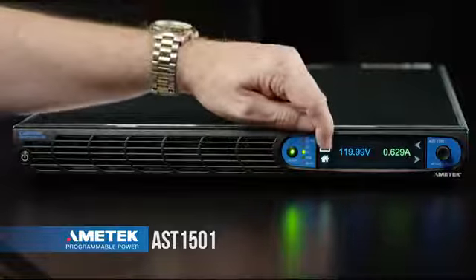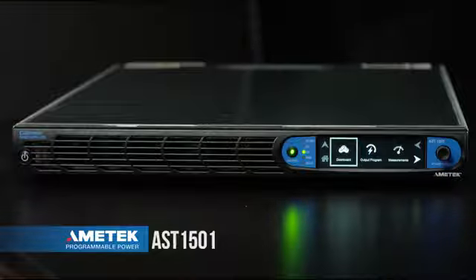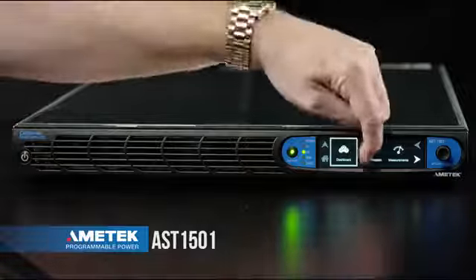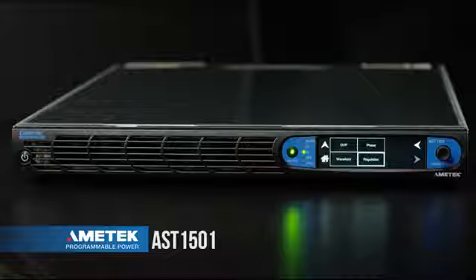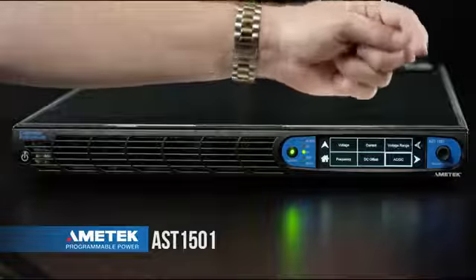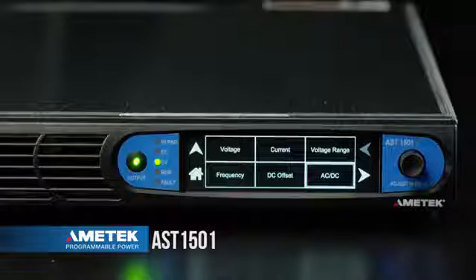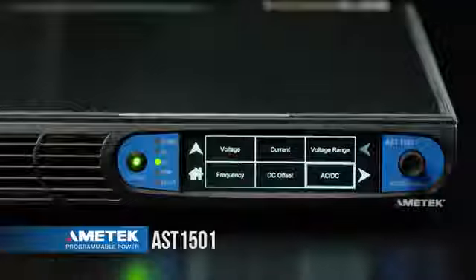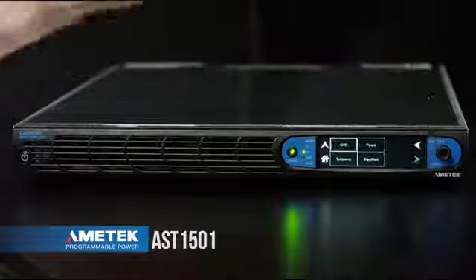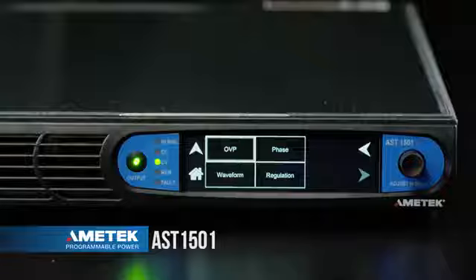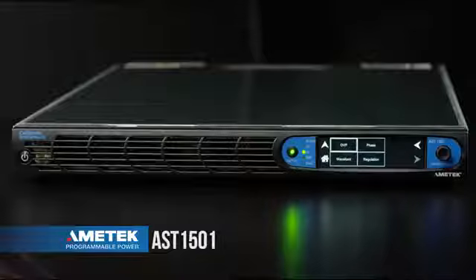Next, we're going to go back to the home screen. Next up on our listed menu is Output Program. Selecting Output Program allows us to select our output parameters, starting with voltage, current, voltage range, frequency, DC offset, and AC plus DC mode. Selecting the right arrow takes us to overvoltage programming, phase angle programming, waveform selection, and regulation mode. We'll go back to our home level menu.